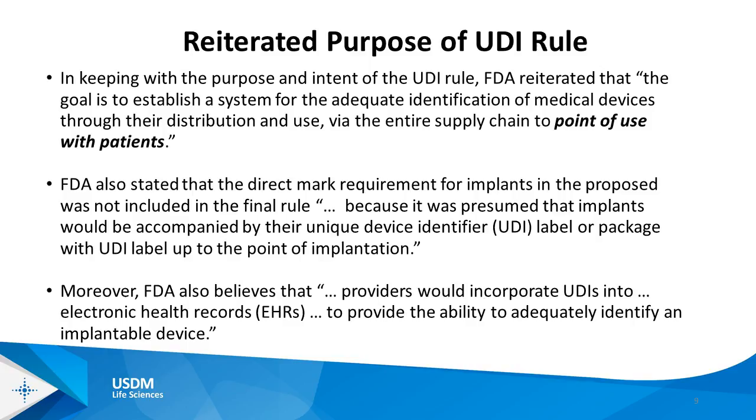I'm not just looking to see where that device is, but that I have the ability to identify a specific device at the point of patient use. So that's always been the goal. That has been stated many times, but I think the FDA has reiterated that point, particularly as it relates to these devices.